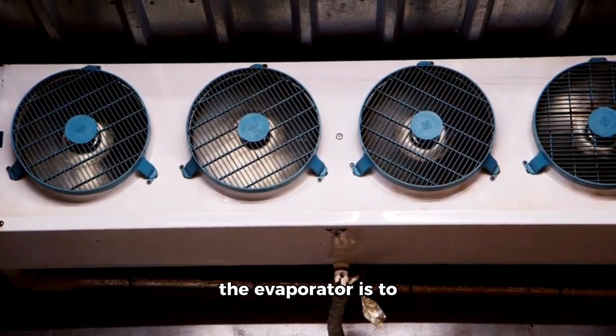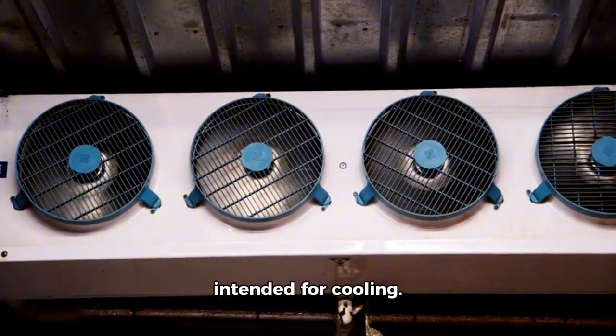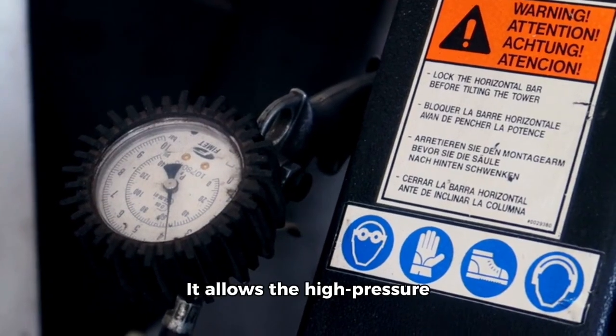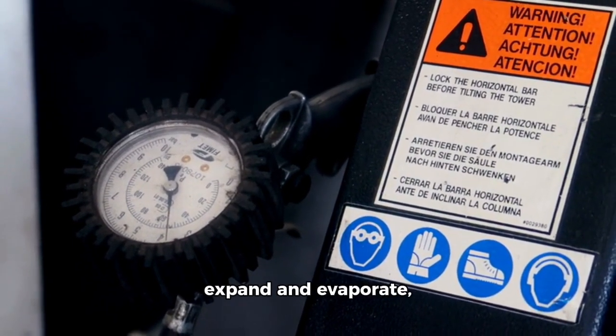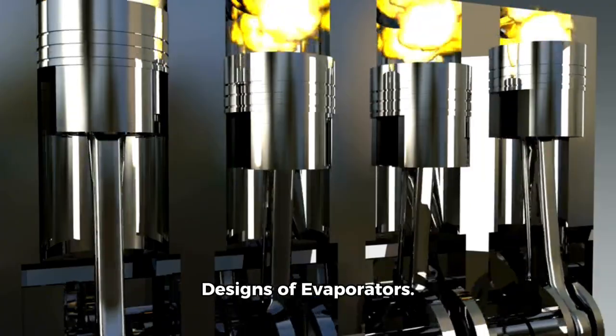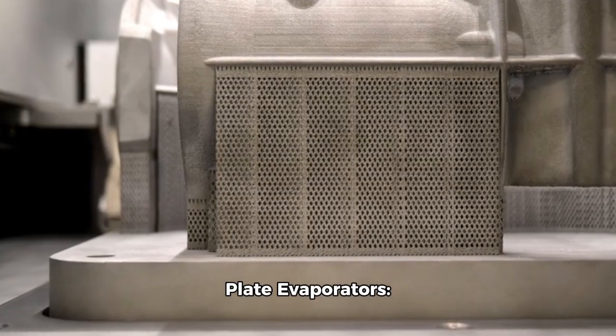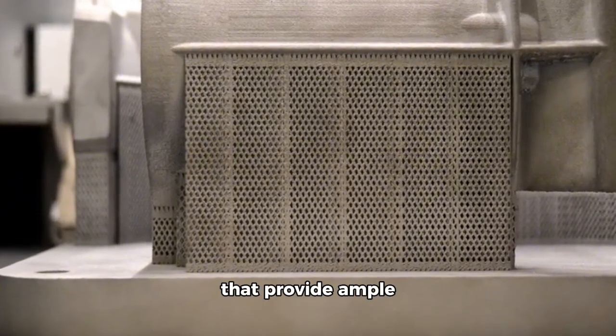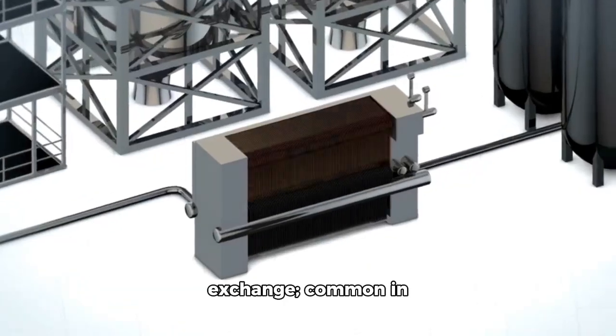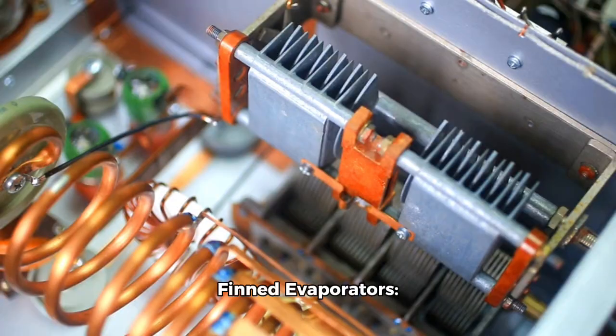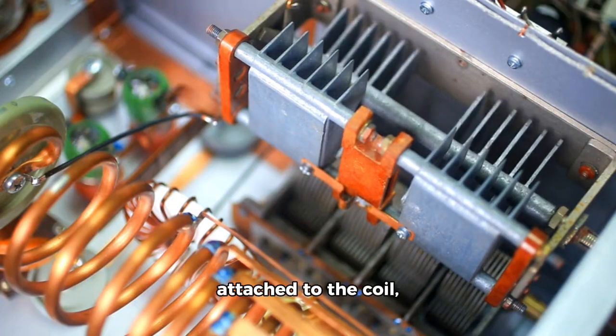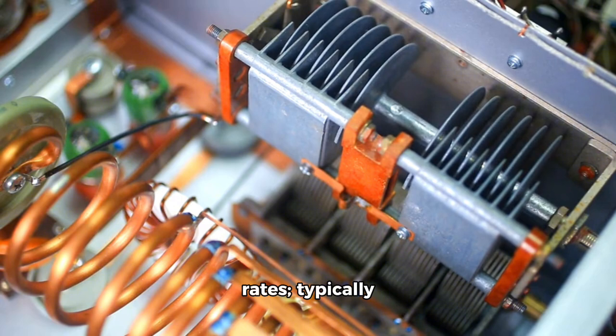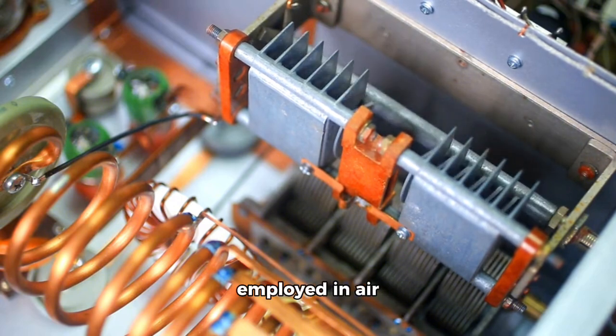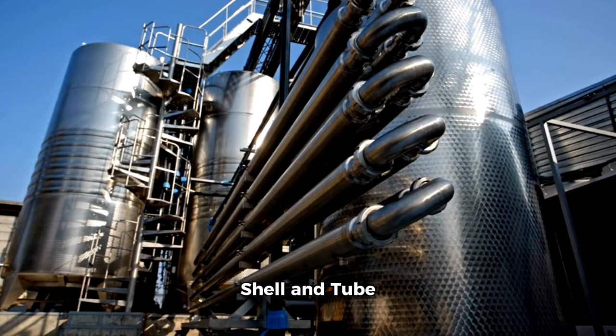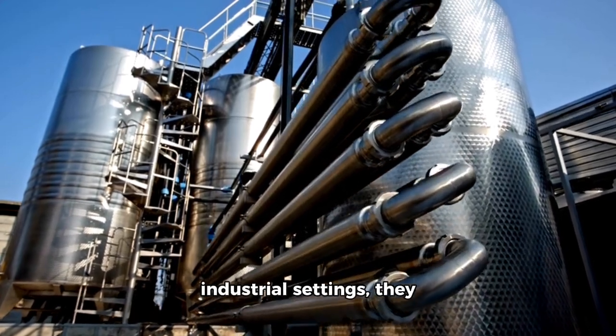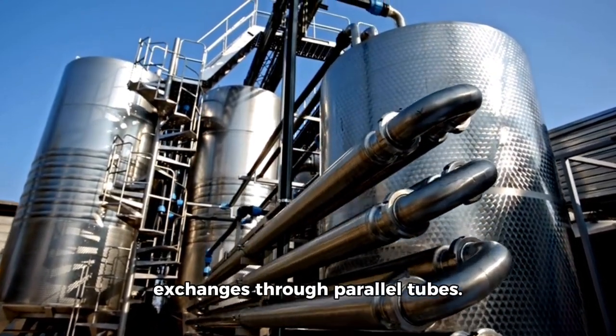Evaporators. The role of the evaporator is to absorb heat from the space intended for cooling. It allows the high-pressure liquid refrigerant to expand and evaporate, turning back into a gas. Designs of evaporators. Plate evaporators feature flat plates that provide ample surface area for heat exchange, common in domestic refrigeration. Finned evaporators consist of metal fins attached to the coil, enhancing heat transfer rates, typically employed in air conditioning systems. Shell and tube evaporators, used in industrial settings, allow for large volume exchanges through parallel tubes.